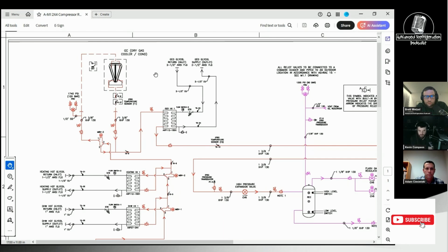It seems like drop leg temp, they seem to hunt more, because when you get a fan kick on, you get that instant drop in drop leg temp, and then you get this hunting going on. Whereas with pressure, you get a little bit more of a buffer. Saturation doesn't drop as fast. Kevin and Brett, I've recently been doing some testing very specifically on this, and I've seen very positive results by controlling on pressure rather than temperature, and for good reasons, right? From a pressure standpoint, it's immediately reactive. So if a fan increases or decreases in speed or cycles on or off, that pressure is instantaneously affected.